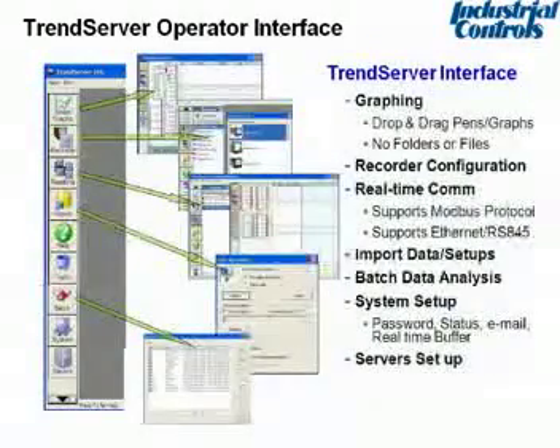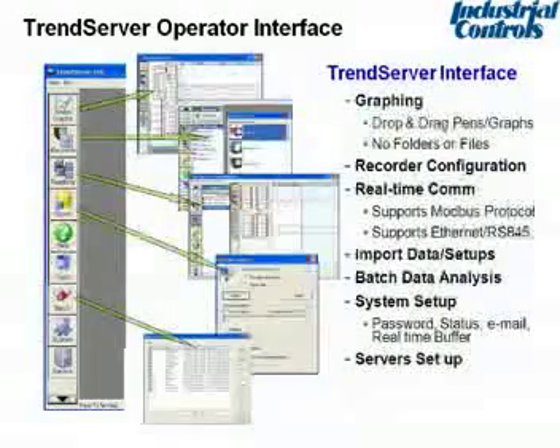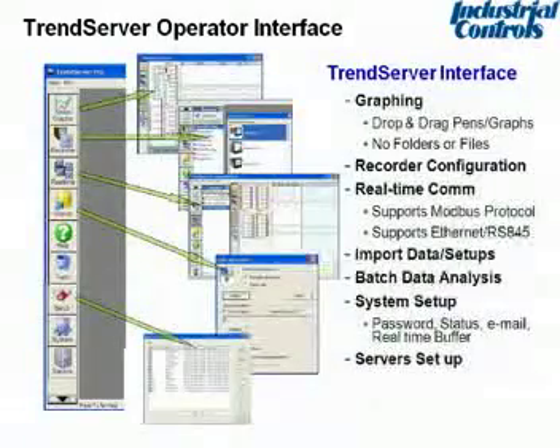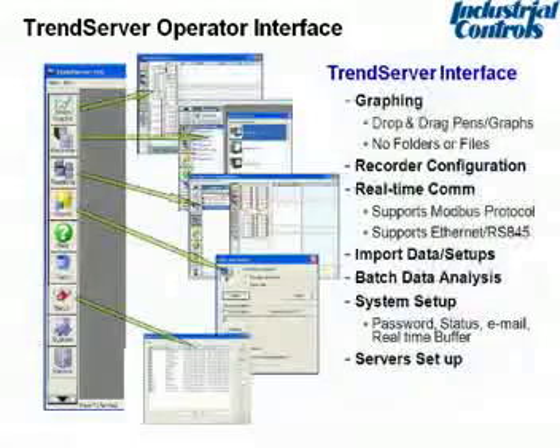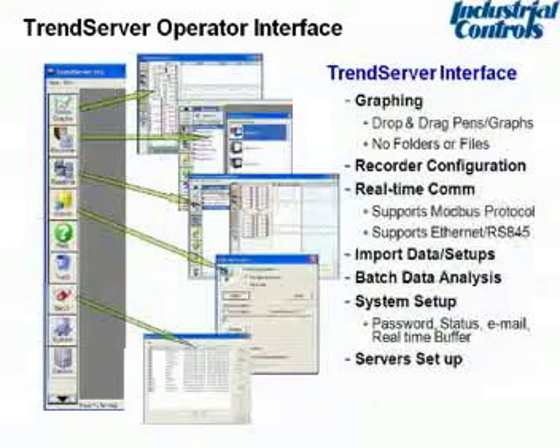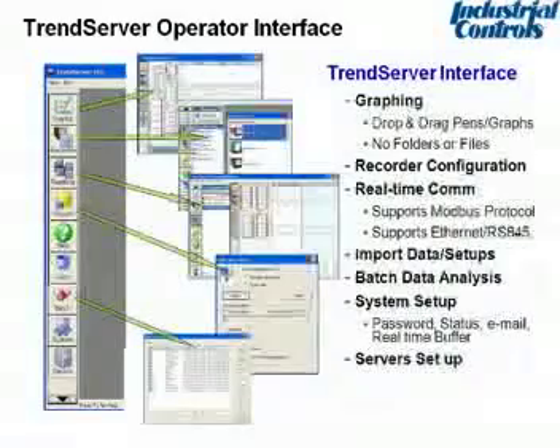It also has the capability of doing analysis by going back in time. So when you bring that data up into the Trend Server Pro, I do this a lot on a startup, I'll look at the trend of the process, do a print screen, and copy it into an email, and I can send the actual time from that particular parameter to my production guy, my maintenance guy, or my customer. So a lot of capabilities there, plus the file transfer protocol we talked about earlier.